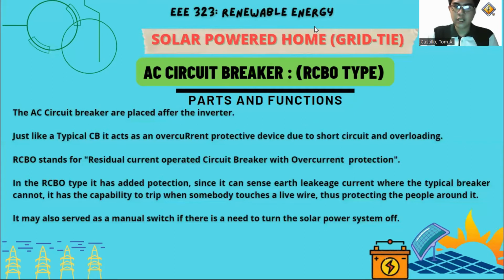RCBO stands for Residual Current Operated Circuit Breaker with Overcurrent Protection. The RCBO type has added protection since it can sense earth leakage current, where a typical breaker cannot. It has the capability to trip when somebody touches a live wire, thus protecting the people around you. It also serves as a manual switch if there is a need to turn the solar power system off. So the RCBO differs from the MCB, like the one earlier for DC: the MCB can provide protection against overcurrent and short circuit only, while the RCBO can provide protection against overcurrent, short circuit, and earth leakage current.